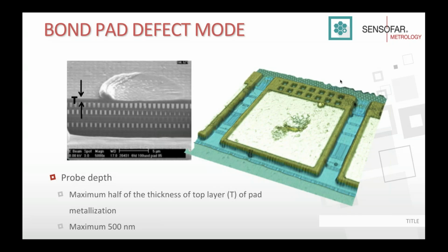And we can measure this with a single field of view relatively quickly using our interferometer. And we can determine the depth of the bond pad impression.